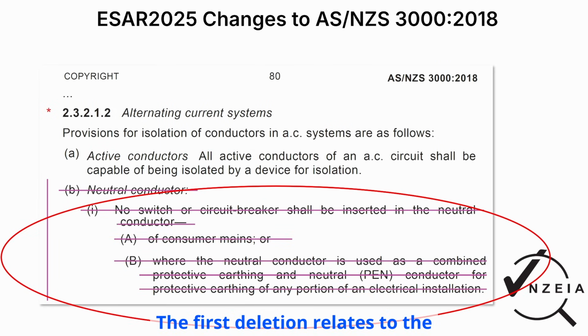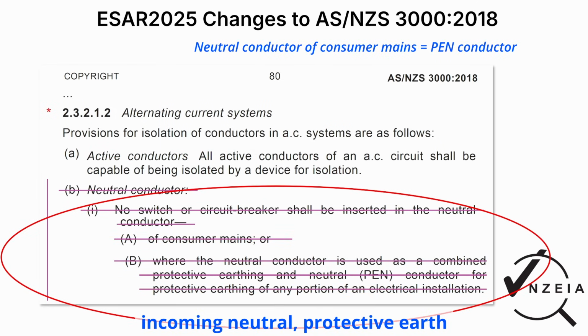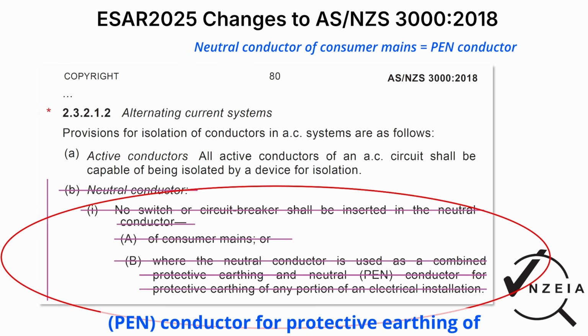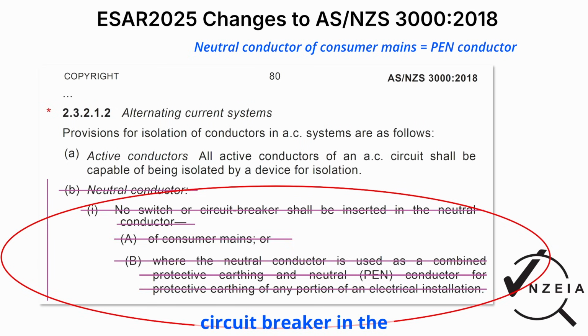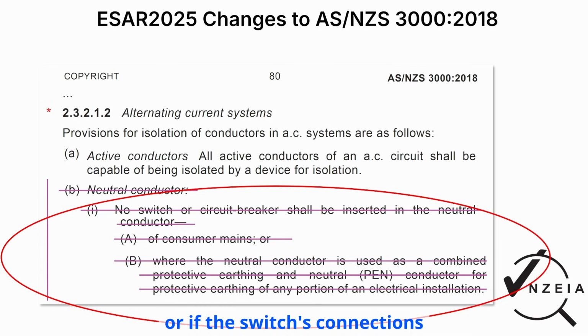The first deletion relates to the incoming protective earth neutral of an installation. "No switch or circuit breaker shall be inserted in the neutral conductor of A, consumer mains, or B, where the neutral conductor is used as a combined protective earthing and neutral PEN conductor for protective earthing of any portion of an electrical installation." With this deletion, it is now compliant to install a switch or circuit breaker in the PEN conductor. In the off position, or if the circuit breaker trips, or if the switch's connections or contacts fail, the installation becomes lethal. This is extraordinarily bad from a safety regulation perspective.